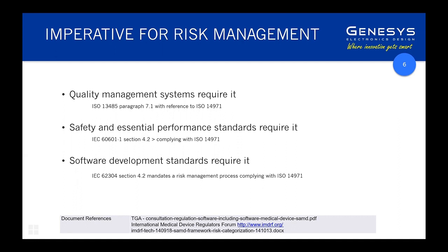So getting back to some specifics of where we link risk management into the medical device development process, we've identified 3 key linkages. Risk management is recognised in ISO 14971, in ISO 13485, ISO 14971 is recognised, but it's not specifically mandated, which is interesting.